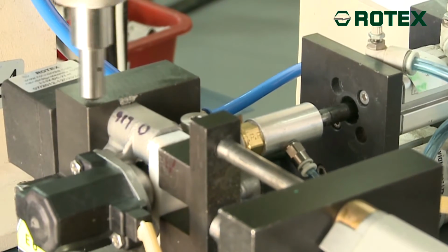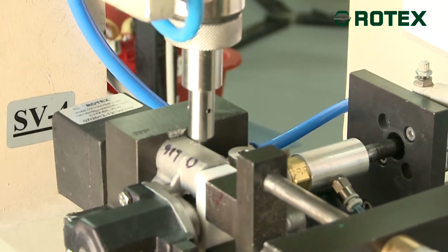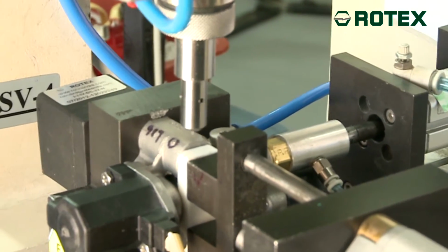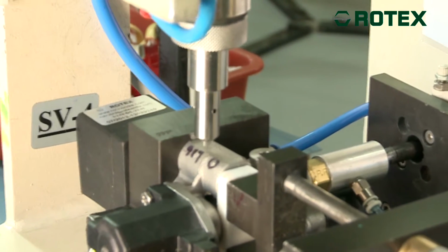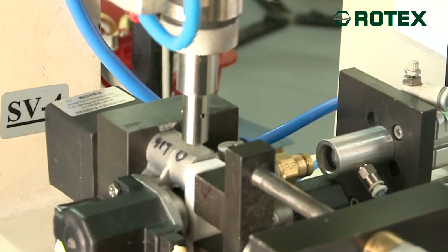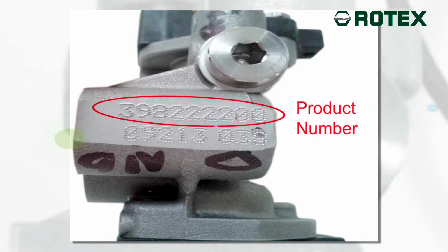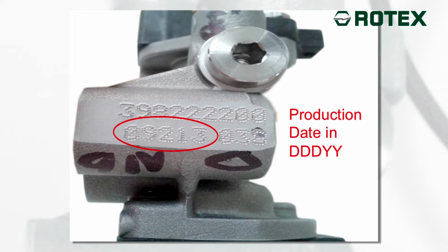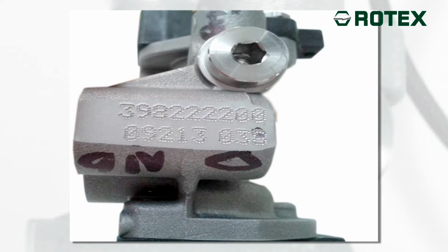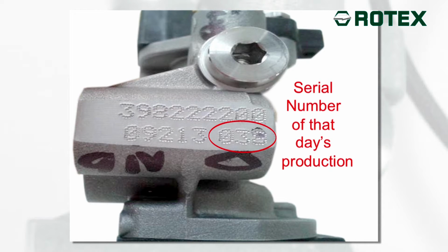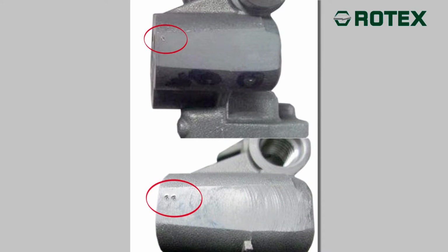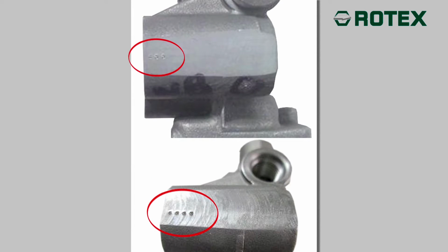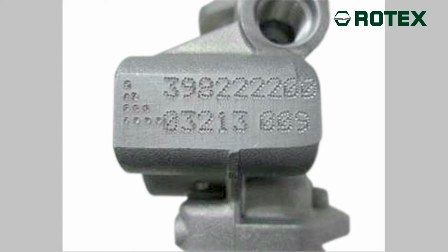Marking. There is a serial number and product number marking, which will provide complete traceability of all performance parameters measured during the test. Serial number will not be marked if the valve does not pass all the tests. Also, there will be an error code marking if the valve fails one or more than one test. Thus, when such valves are reworked, they are traceable with these markings.